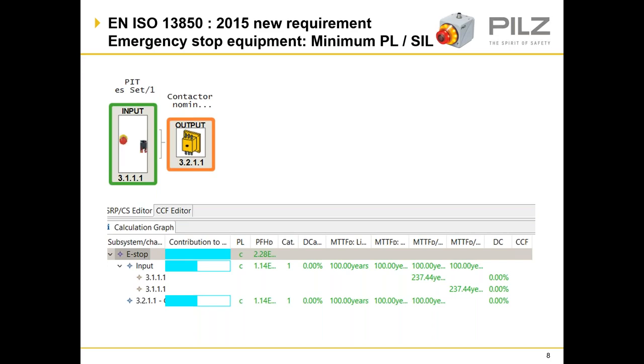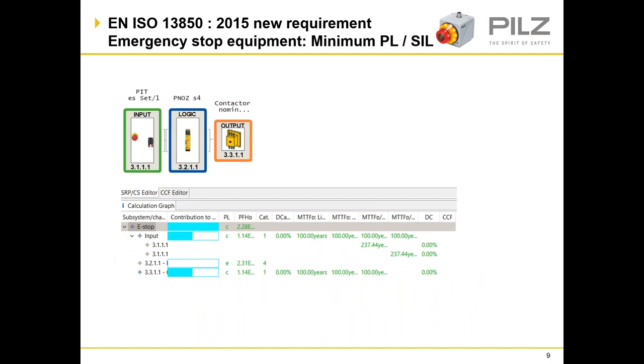A single contact dropping out a contactor may be completely acceptable, but this is based upon the risk assessment and hazard identification to determine the appropriate safety related control system requirements. In this second scenario we again have a single channel e-stop but have now included a safety relay to monitor the e-stop loop. We are still using well-tried and tested components and still only have one contactor disconnecting our load. Without feedback from the contactor, we still have a diagnostic coverage of 0%, and without diagnostic coverage we cannot exceed a category 1 architecture, so the maximum performance level is still performance level C.